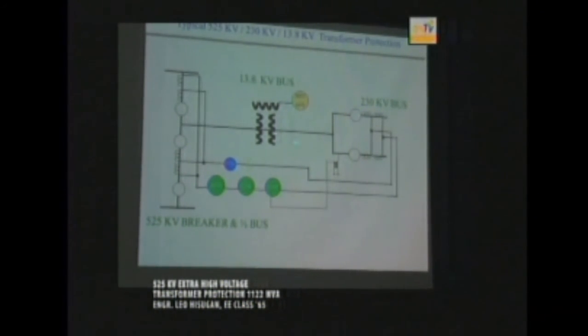So when we set the relay at the low side of the bank here, our phase distance protection is set at 67% for your zone 1, which is instantaneous protection, 0.0 seconds. Your zone 2 is set at 0.33 to 0.5 of a second in order to coordinate with the line protection on your transmission line. So your zone 1 is instantaneous at 0.0 second. Your zone 2 is at 0.33 or 0.5 of a second. Also on the 13.8 kV delta bus here, you will have your tertiary overcurrent protection, phase, time and instantaneous.